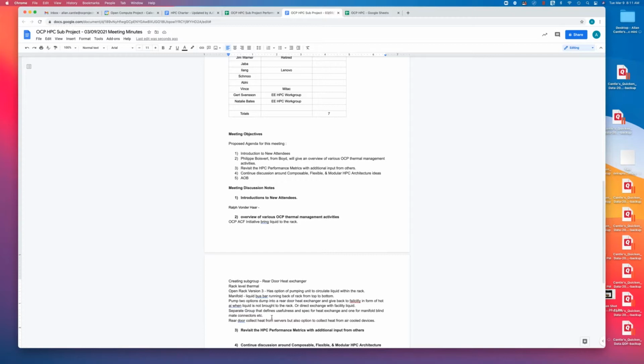The rear door heat exchanger needs to run in only one of two modes: either it dumps a lot of heat from all the CPUs into the facility air, or if there's facility level water available at the rack level, it can be used as an air conditioner for the rack.